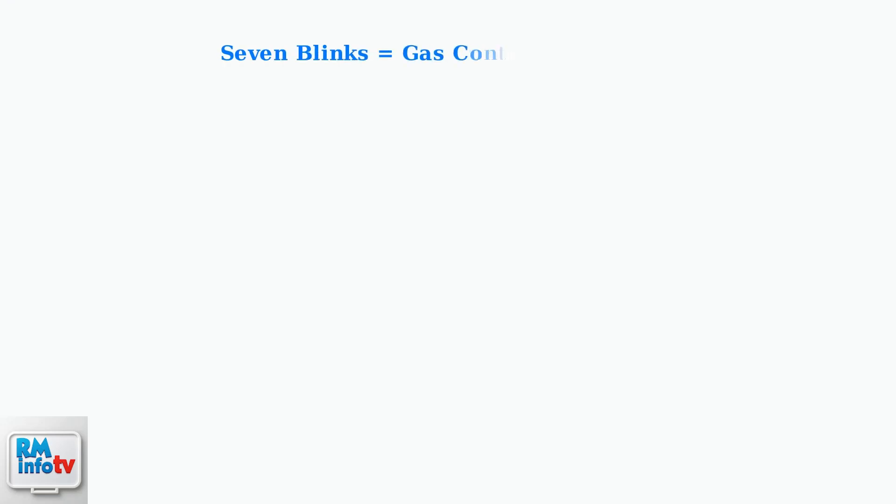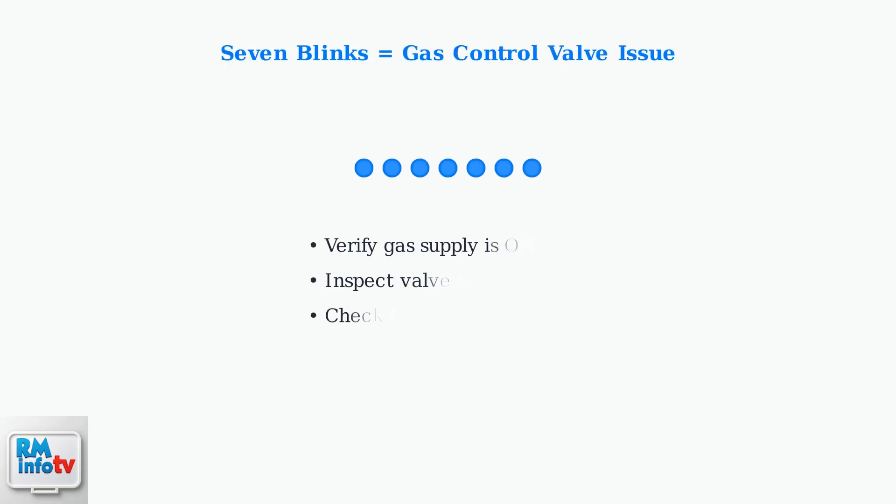For a specific case, if you see seven blue blinks, this typically indicates a gas control valve failure. Verify your gas supply is turned on and visually inspect the valve for any obvious damage or loose connections.